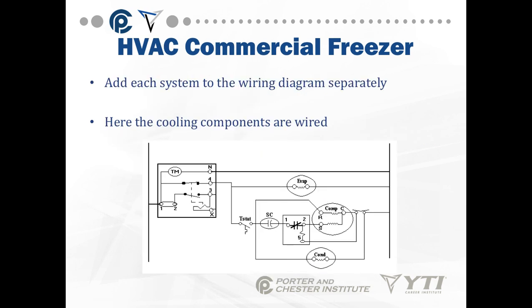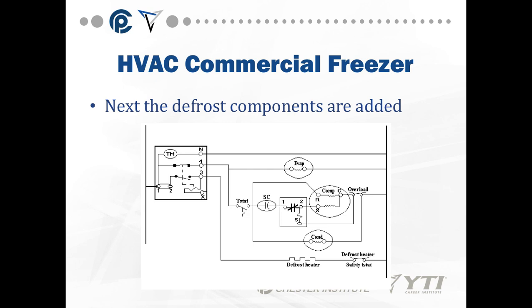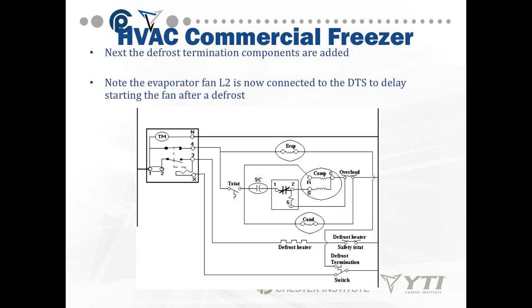Add each system to the wiring diagram separately. First, put in all cooling components. Then start adding defrost components. Then add defrost termination. We use a DTS to start the fan after defrost. Notice this drop from the L2 side of the evaporator fan comes down to the cold side of the DTS.